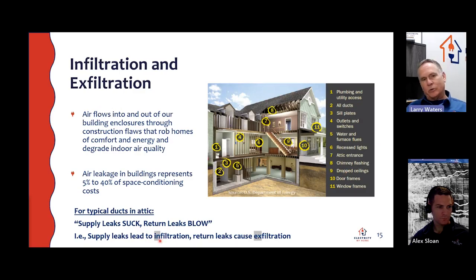Return air leaks, if you have a return in the attic, or you have an uninsulated or unsealed return air cavity that's connected to the interior walls, that's going to create exfiltration because you're not pulling as much air out of the house as you're putting back in, because it's coming from other places. So it's going to incidentally pressurize the house and cause the conditioned air to leak out.